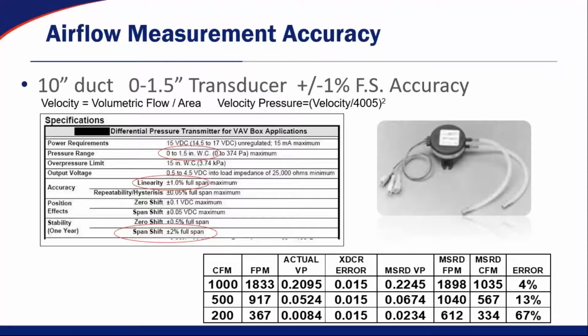Now if we look at the chart there on the bottom, what we're actually measuring with a pressure transducer is the velocity pressure. And that's calculated by the area of the ductwork and the velocity. If you look at the volume of air, 1,000 CFM going through a 10-inch ductwork, you can calculate out that the velocity is 1833 feet per minute. And the velocity pressure is actually a function of a square. And this is where a larger error comes into play, even with a 1% accuracy pressure transducer. So at 1,000 CFM, my velocity is 1833. My velocity pressure is the velocity of the air divided by a constant of 4,005, and then that number squared. So the velocity pressure at 1,000 CFM is 0.2095.